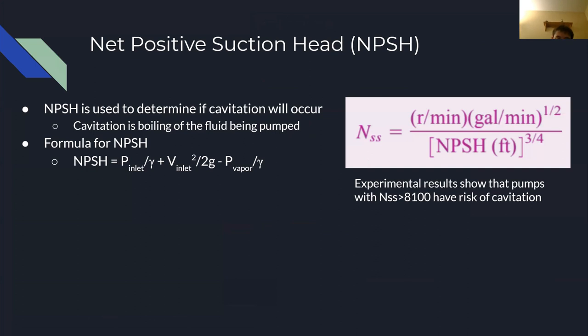Net positive suction head is the effective fluid height above the inlet of a centrifugal pump required to prevent cavitation. Cavitation is the process by which the fluid being pumped boils inside the pump due to the local pressure falling below the vapor pressure of the fluid.